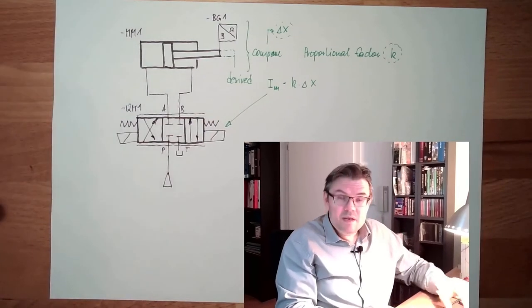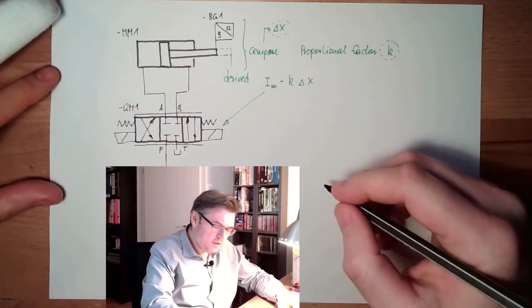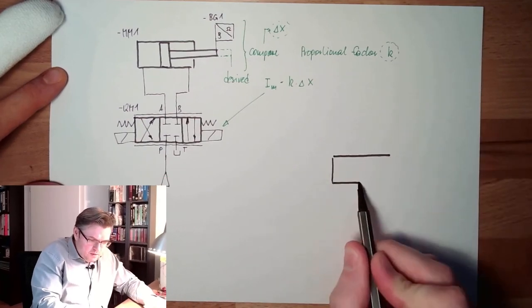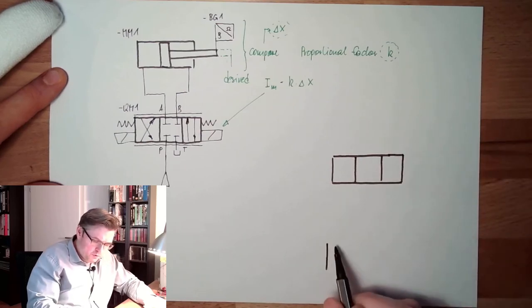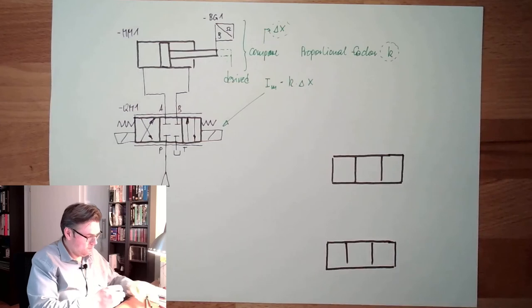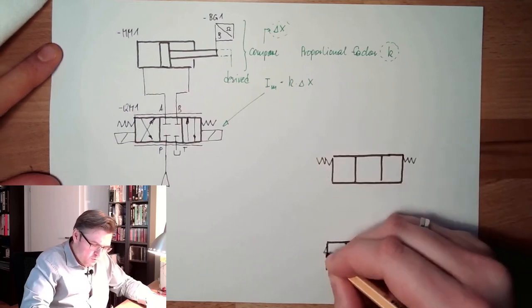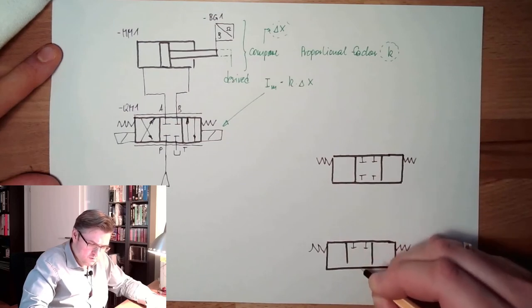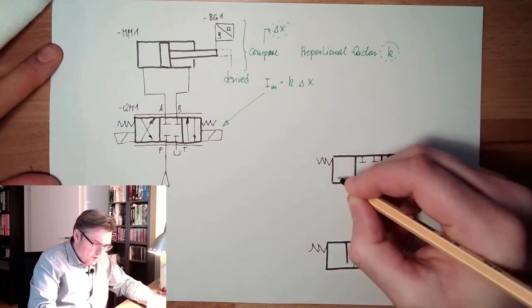Positioning control loop. What if this is a really big cylinder? Then we do it with a two-stage hydraulic. It looks pretty much like that. So there is the cylinder on the top, I will not draw it. However, there is a big proportional valve and there is a smaller proportional valve. Both are centralized or both are put to middle position with the help of springs. The middle position is blocked at both. Straight position, so they are really looking quite the same way.